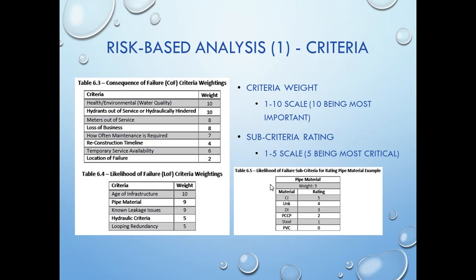From that, we developed a consequence-of-failure criteria and a likelihood-of-failure criteria: water environmental quality issues, hydrants out of service or hydraulically hindered - those are big issues, they get a weight of 10. Meters out of service get an 8, as you can see in the list. Location of failure is a 2, because almost every location could be fairly devastating, but some less than others, so the weighting is lower. We worked back and forth with Addison to come up with the best weightings for evaluating their CIP.